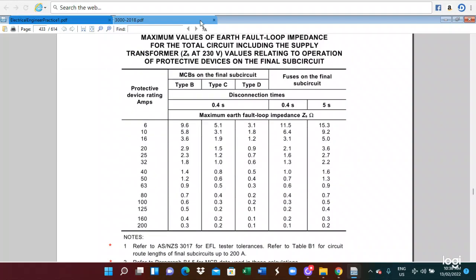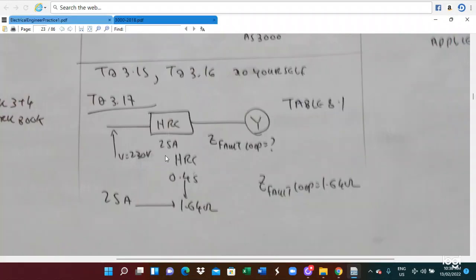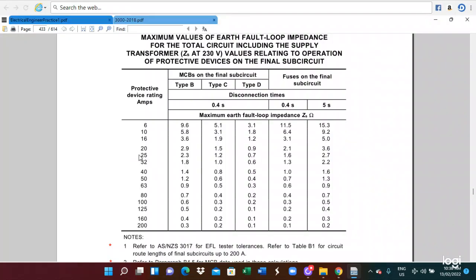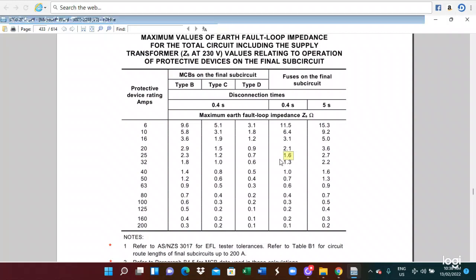Table 8.1 means that if you are installing a fuse on the final sub-circuit, there are two kinds of fuse. An HRC fuse has a 0.4 second operation time, and a normal fuse has a 5 second operation time. In this problem, we are given a 25 ampere rating and an HRC fuse, 0.4 second. You can see the value in ohms. So the fault loop impedance is given in ohms. From here you can calculate like this.